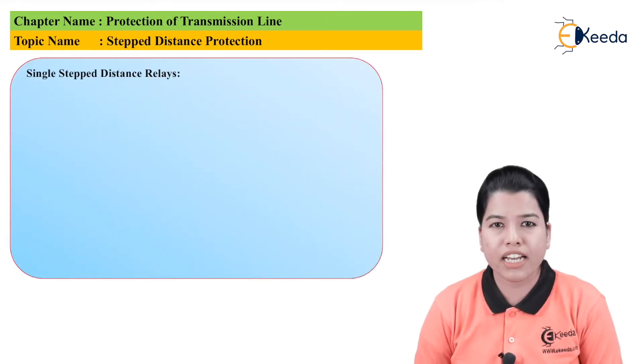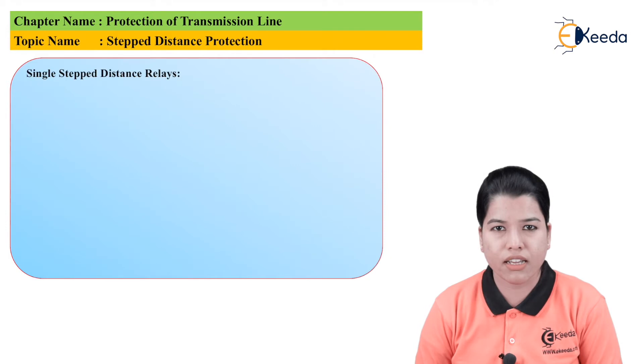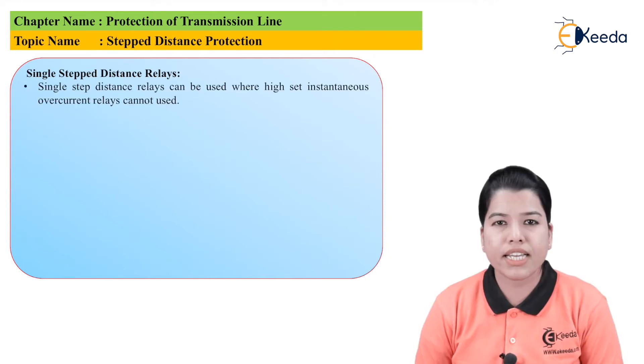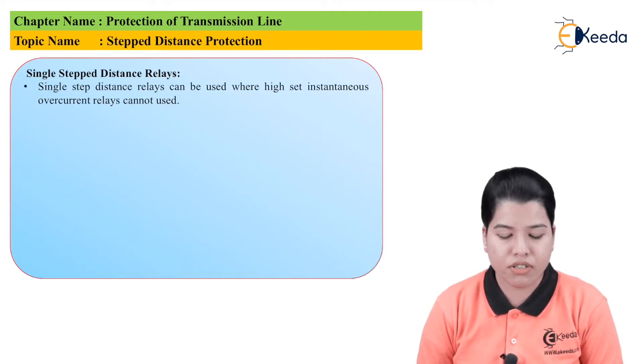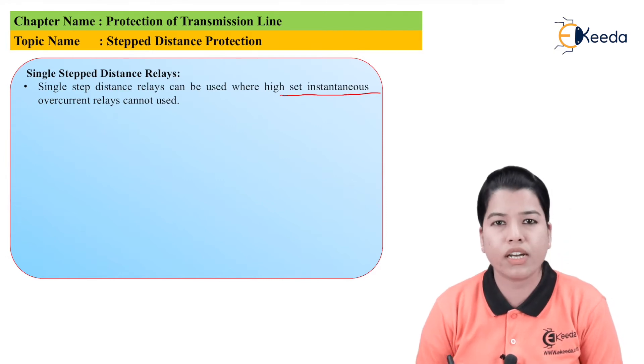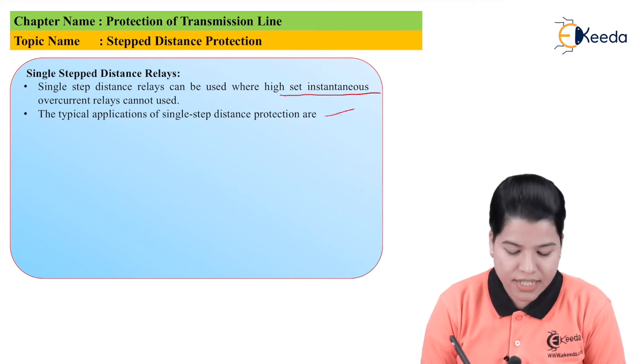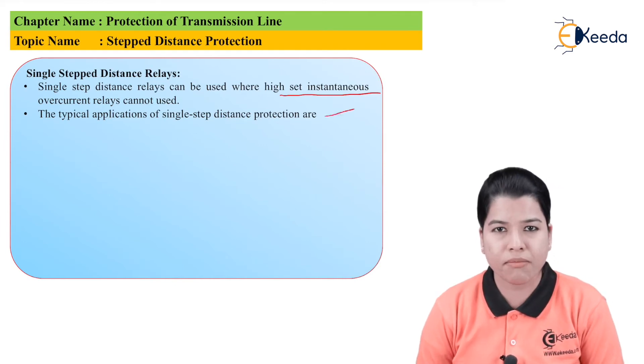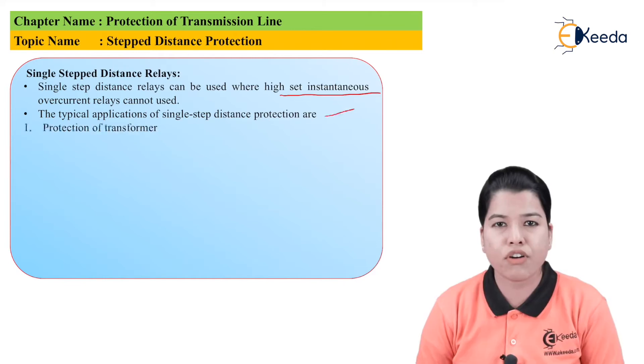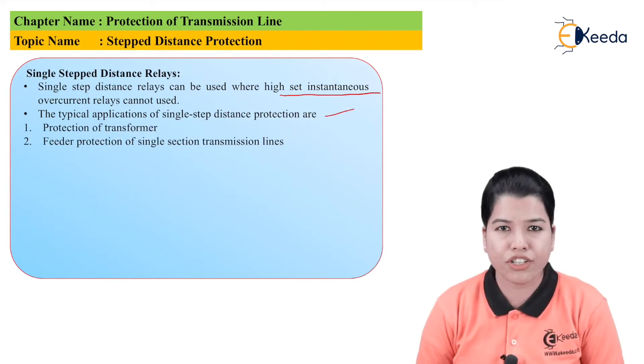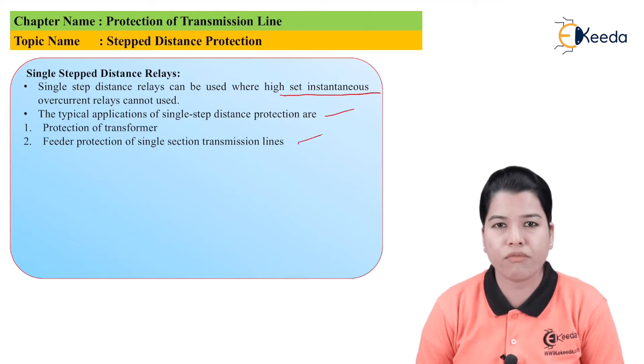Now let us study about the single stepped distance relay. The single stepped distance relay can be used where high-set instantaneous over-current relays cannot be used. The typical applications of the single step distance relay in the power system are: first, for the protection of transformers; second, for the feeder protection of a single section of transmission lines; and third, for the protection of bus bars.